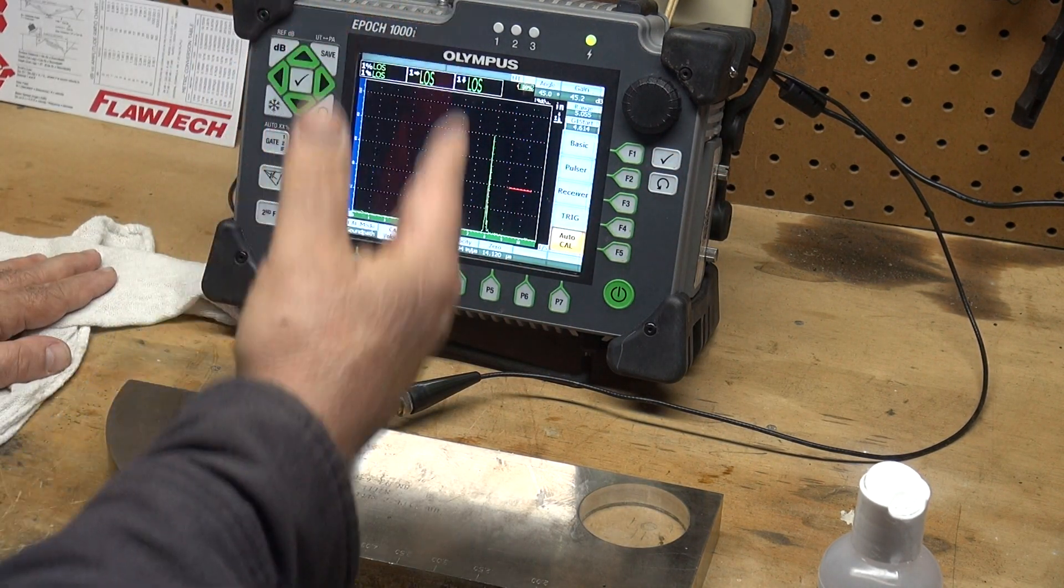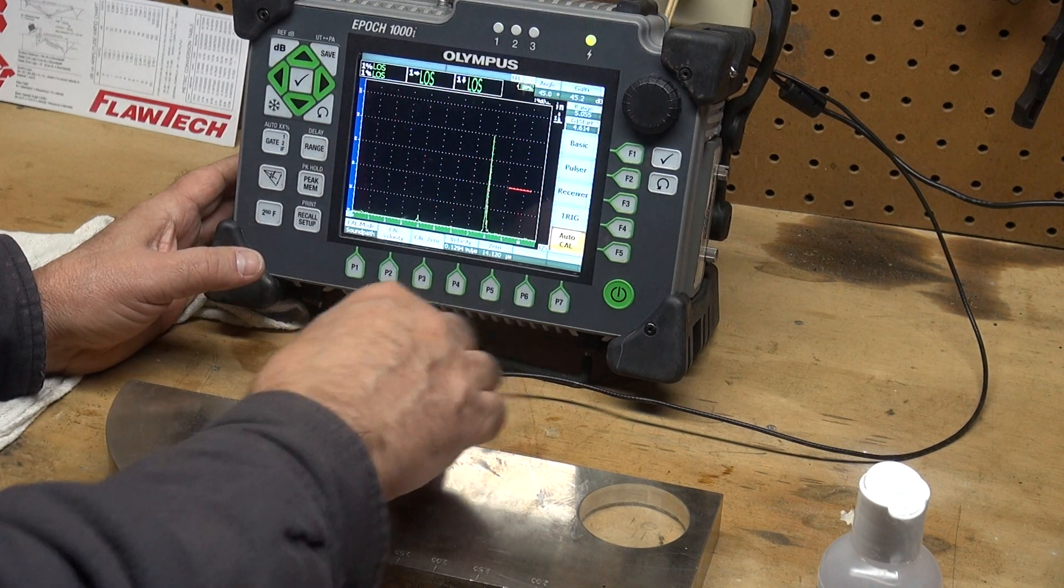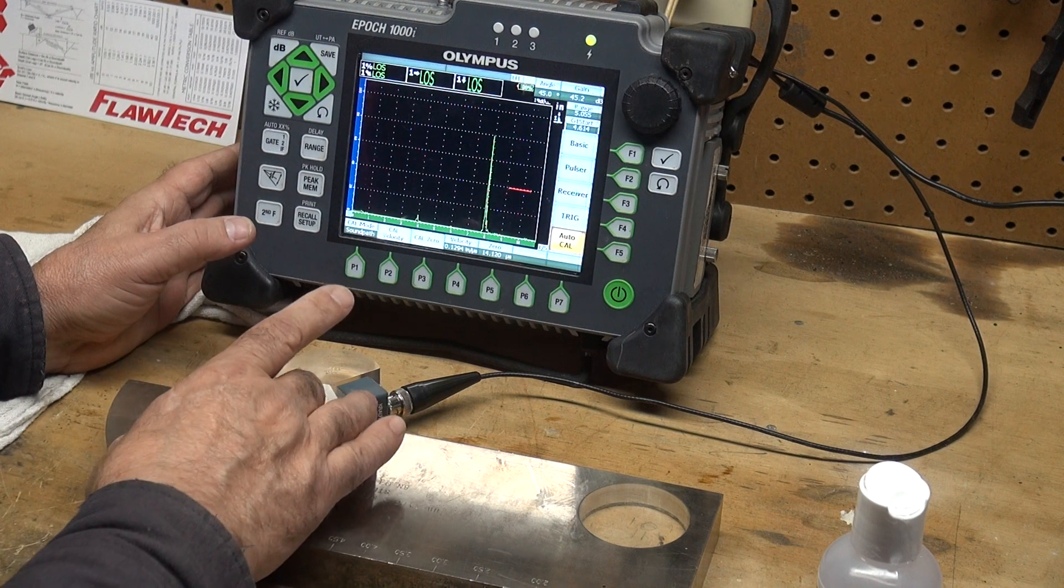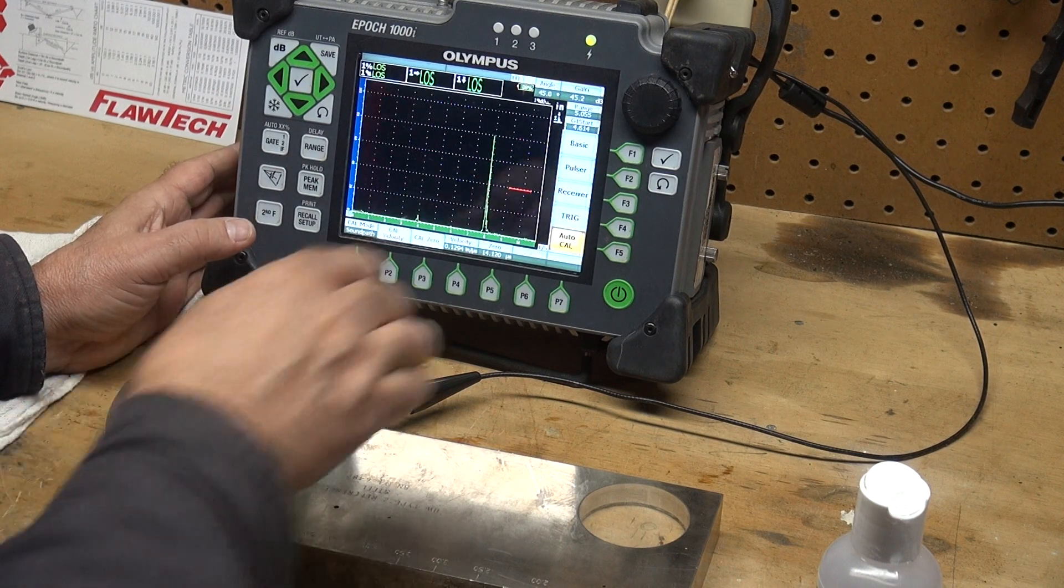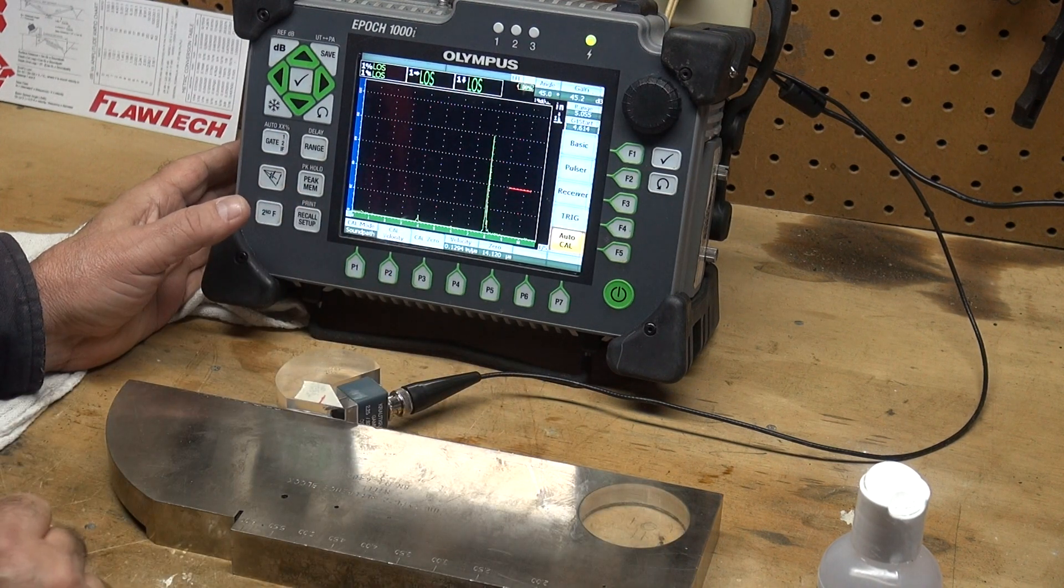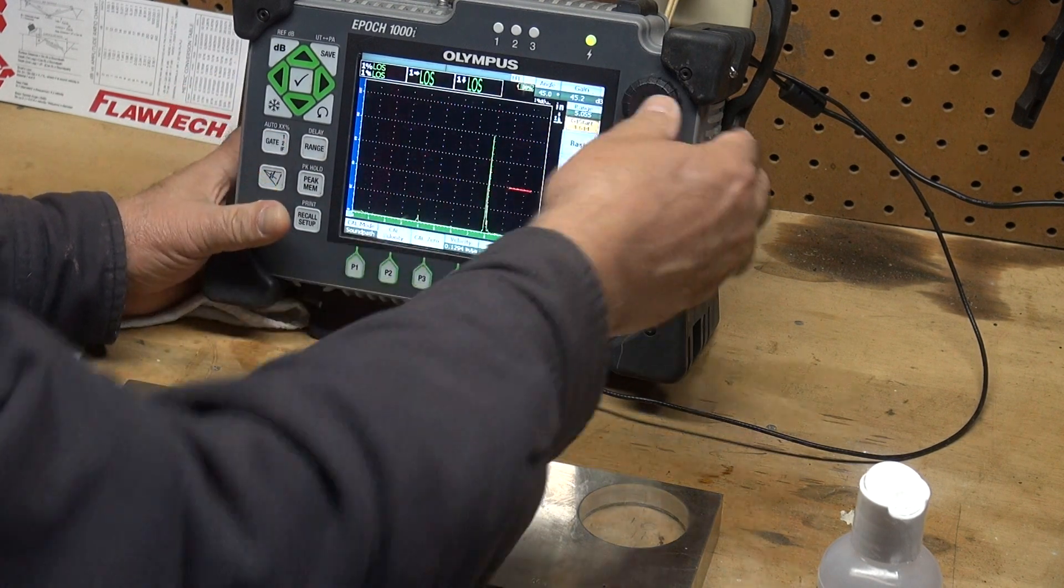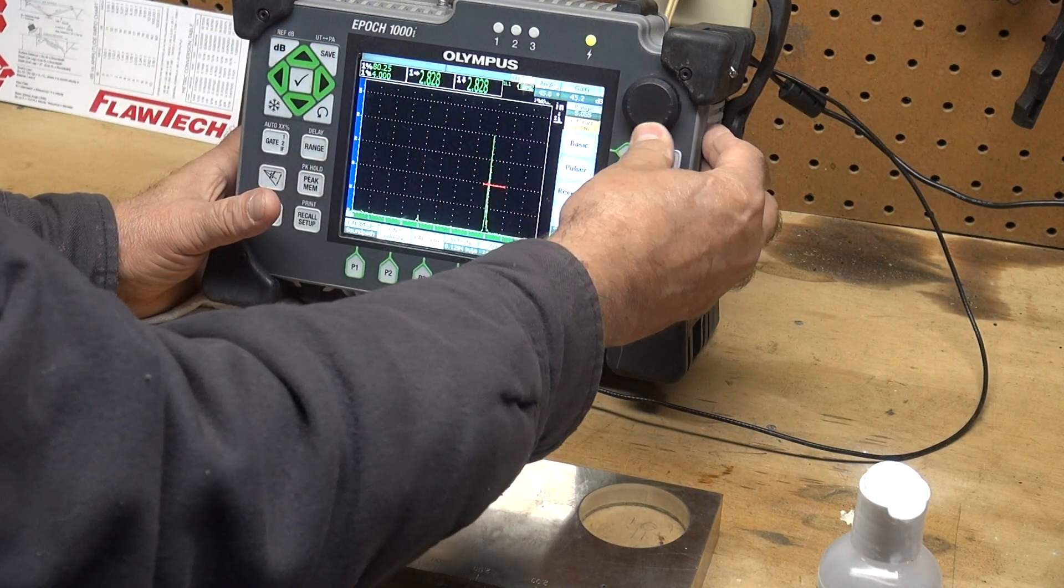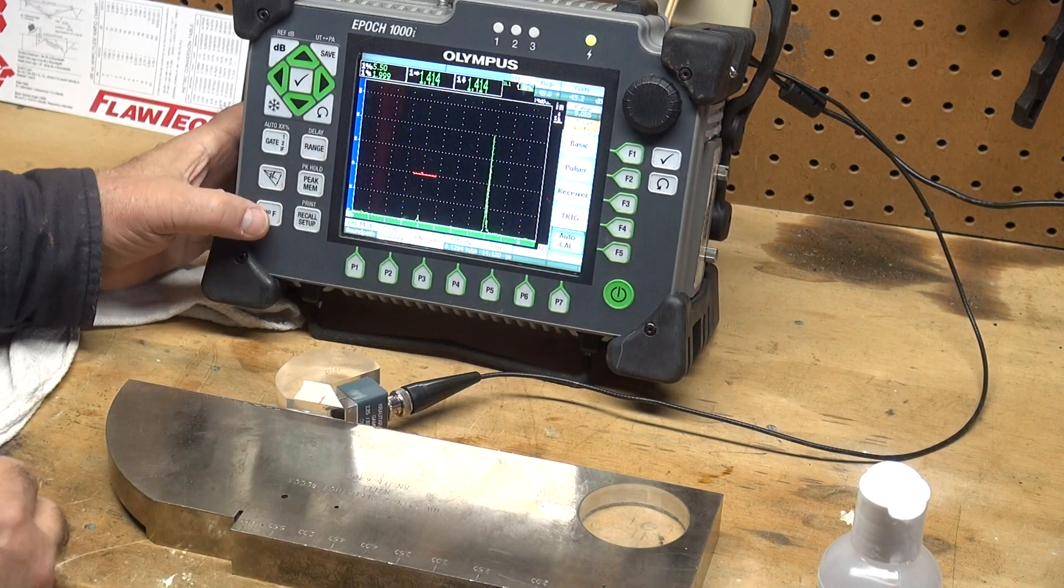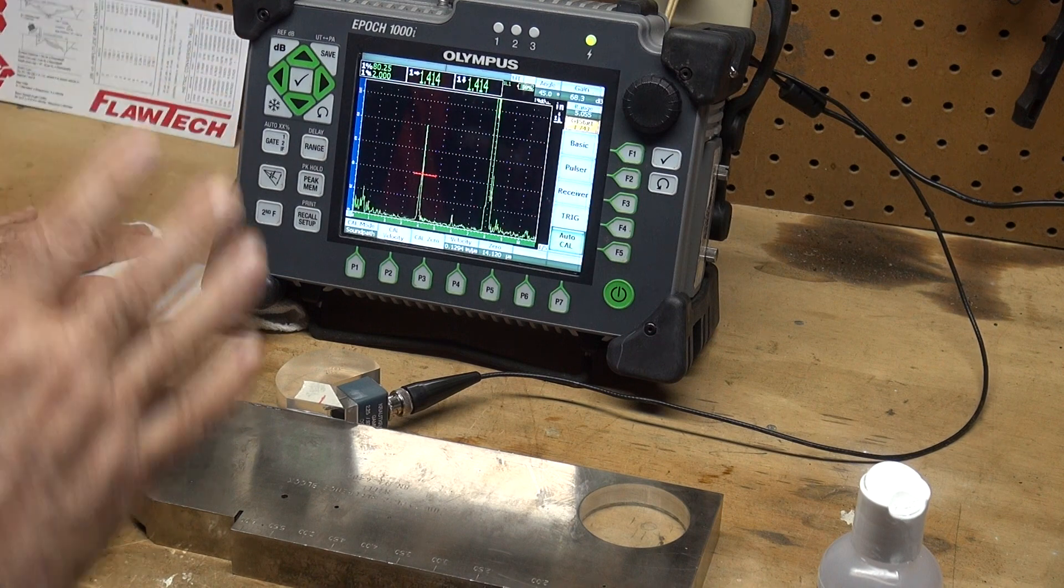In this case, the zero is 14.12 microseconds. That's how much time is spent in the wedge. The velocity for this IIW reference block changed from 0.128 to 0.129 inches per microsecond. I can double check by bringing the gate over my 4 inch radius, it shows 4 inches, and bringing the gate over to my 2 inch radius, it's right at 2 inches. So now our machine is calibrated.